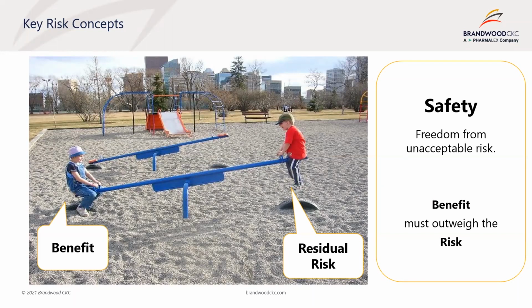An example of a benefit and risk analysis is when burns can occur where the return electrode of a high-frequency surgery device is improperly attached to the patient. Although conformance to the relevant product standard minimizes the probability of such burns, they can still occur. Nevertheless, the benefit of using a high-frequency surgery device outweighs the residual risk of burns.